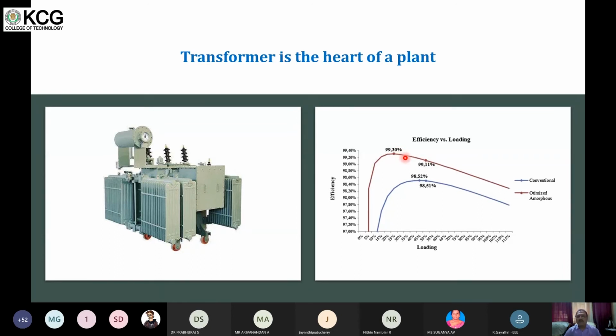So therefore, whenever you come across a transformer which is loaded close to the nameplate, you should realize that the efficiency drops down by more than 2%. And therefore, it is important to keep the loading pegged between 35 to 50%. So the point I'm trying to bring out, the first task we undertake in an audit, whenever we have an opportunity to assess the potential for energy saving in an industry, is to look at how the transformer is loaded. I will give you one example.